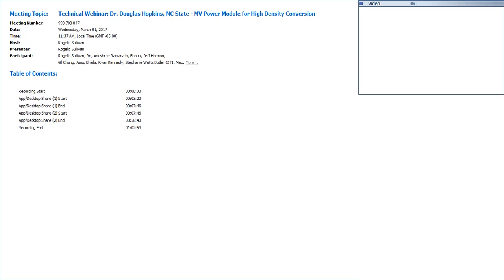I had a question. There was a slide where you showed 457 watts per centimeter square, and I was wondering with the cooling that you're capable of doing, how many watts per centimeter square can you dissipate? I'm looking for a rough answer. From our computational dynamic simulation, we get a junction to liquid thermal resistance of about 0.5. That's based on the die size of 5.5 by 3.5, so that's about 1/4 of a square centimeter. If you convert it to 1 square centimeter, that's roughly 4 or 5 times better, corresponding to 0.1 something degree C per watt for liquid.